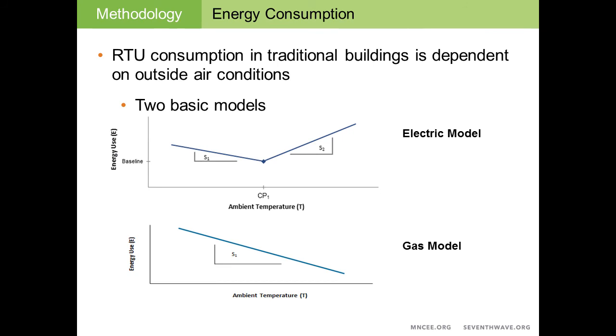So the energy consumption data was pulled back. It was summed for an entire day and then related to outdoor air temperature. And we were looking for two basic models that are set up for energy consumption. The primary models are the electric, which has a change point, and above that change point to the right is a cooling component, and to the left is generally just the fan component. In the gas model, it's generally just a linear curve. So the energy consumption of a rooftop unit is primarily driven by ambient outdoor air temperature.